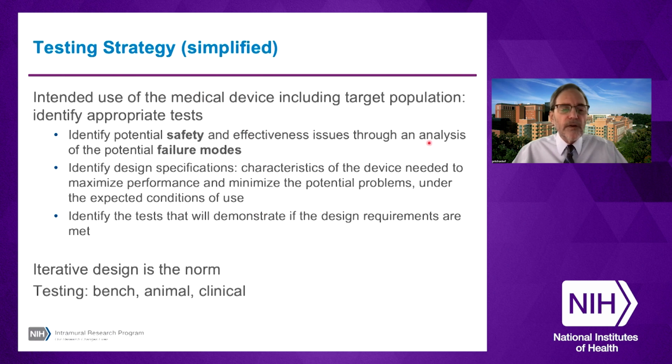And so then you need to identify the design specifications. These are the characteristics of the device that are needed to maximize performance and to minimize the potential problems under the expected conditions of use. And from there, we would identify tests that will demonstrate if the design requirements are met. And these tests could be bench, animal, or clinical testing.